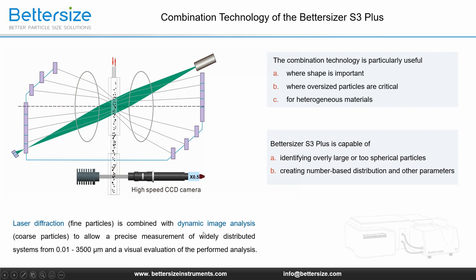However, this combination of two methods is challenging because it requires a powerful optical bench, an ultra-fast and high-resolution camera system, as well as compelling software to process all the information directly online. The Bettersizer S3 Plus uses one of the CCD cameras to photograph and statistically evaluate the coarse particles. The results from laser diffraction and dynamic image analysis are combined in an intelligent routine by weighting based on the concentration determination of both methods. The combined measurement results can then be separated from each other, and the influence of the combination technology compared to pure laser diffraction or pure image analysis can be worked out.